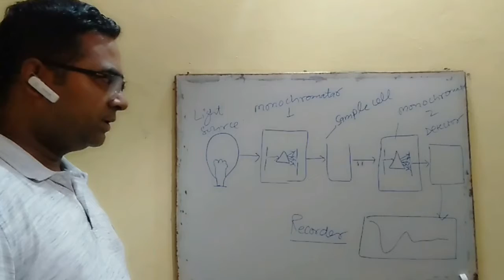Now coming to the instrumentation of the fluorescent spectrophotometer. A fluorimeter is the instrument that measures the intensity of fluorescence, and spectrofluorimeters are the instruments that measure the intensity of excitation and intensity of emission at different wavelengths. The instrumentation of a spectrofluorimeter is similar to what we have seen in the case of the UV visible spectrophotometer. A difference here is that in a spectrofluorimeter, two monochromators are used, one for excitation and another for emission.